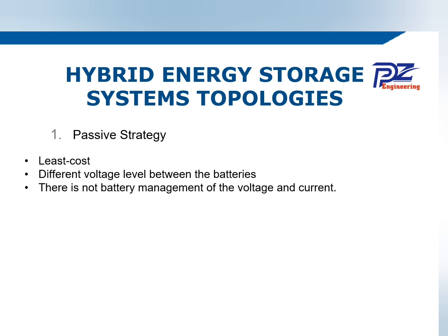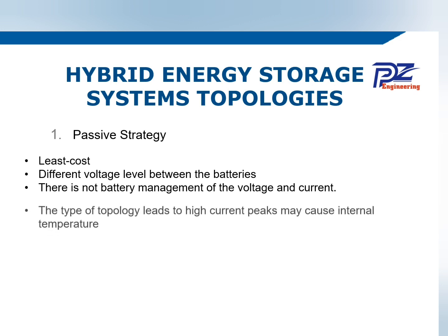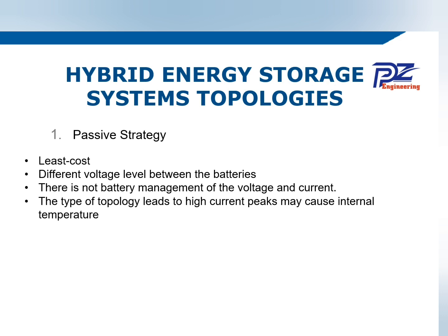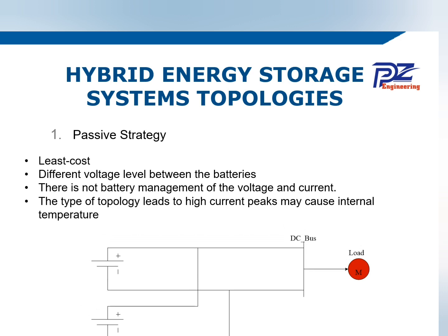The first topology is a passive strategy, which has the advantage of having the least cost. But during differences in voltage level between the batteries, there is no voltage management system in this strategy. This type of topology leads to high current peaks and may cause internal temperature issues because there is not any DC-DC converter controlling it.